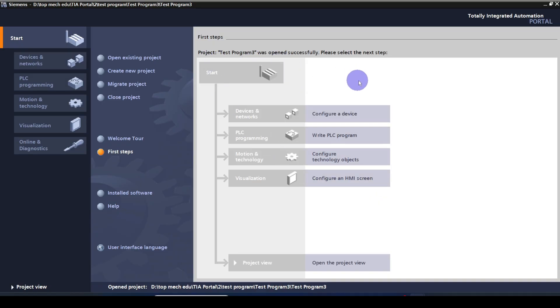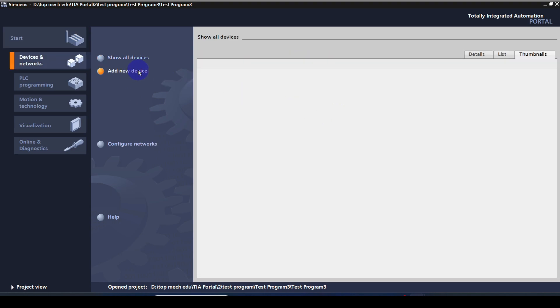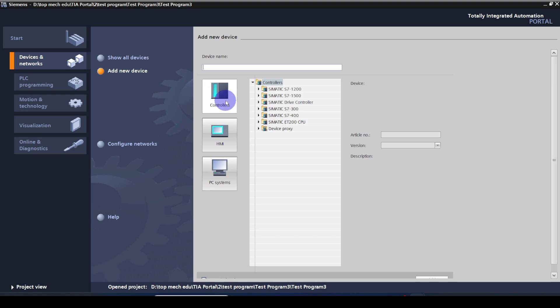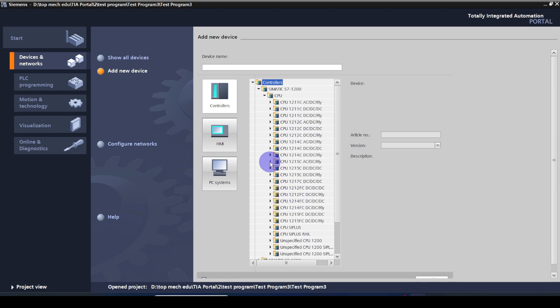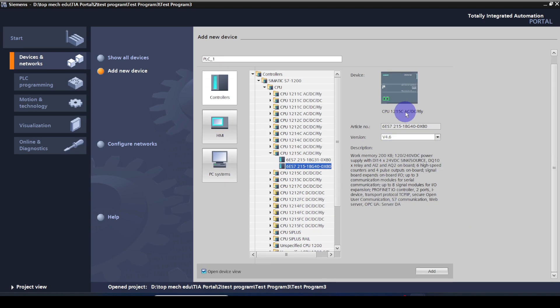To set up the project as a beginner, I strongly recommend following the steps given by Siemens. First of all, configure the device — click on Configure Device, then go to Add New Device. You have to select the controller. Here I am going to select a Siemens S7-1200 type PLC and a CPU model of 1215, version 4.6.